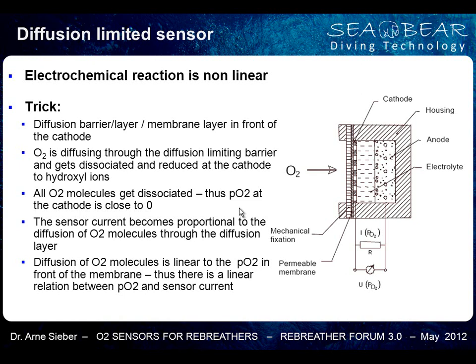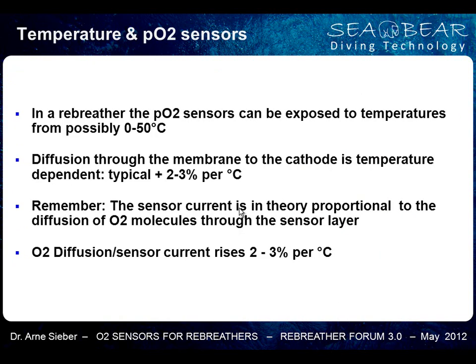What we have is a sensor current that depends only on the diffusion law, the fixed law of diffusion. So temperature and oxygen sensors in a rebreather, the PO2 sensors are exposed to temperatures from possibly 0 to 50 degrees Celsius. For example, if I'm on a mountain lake in winter and take the rebreather out of the cold car, it might have 0 degrees when I start the calibration, and then at the end of the dive it might have 50 degrees. So the diffusion of oxygen molecules through the membrane is temperature dependent.